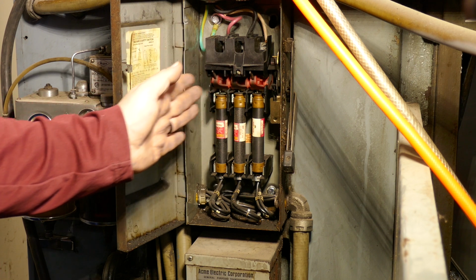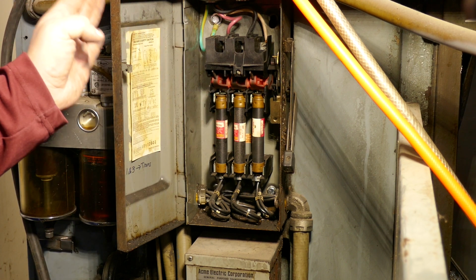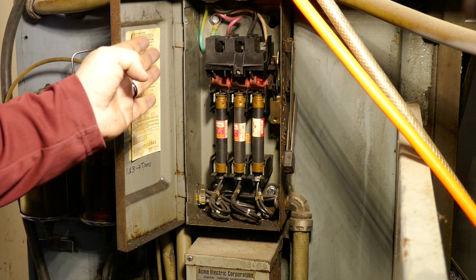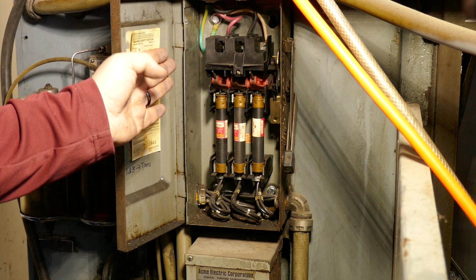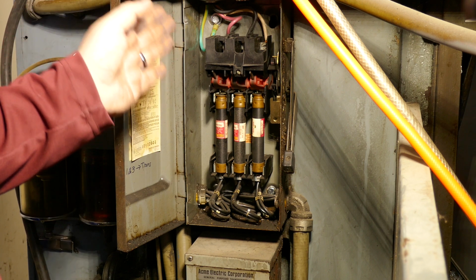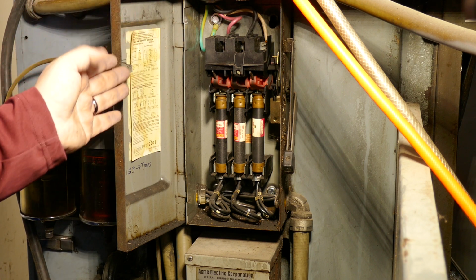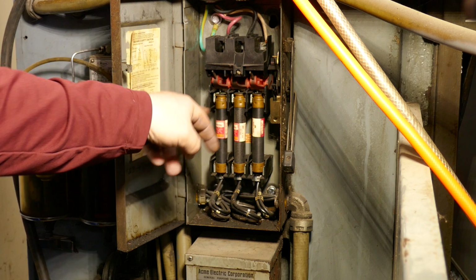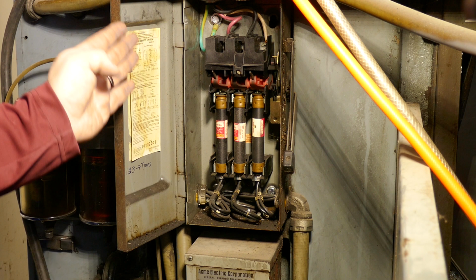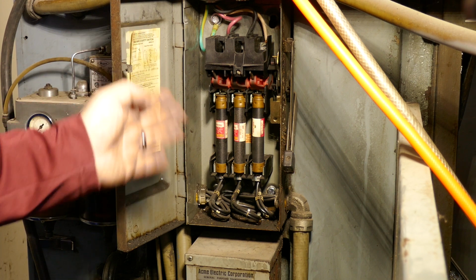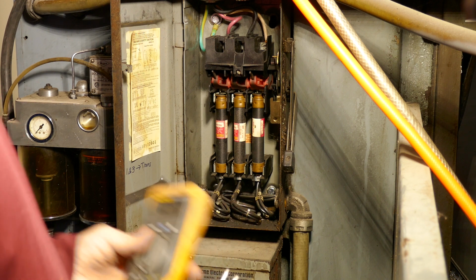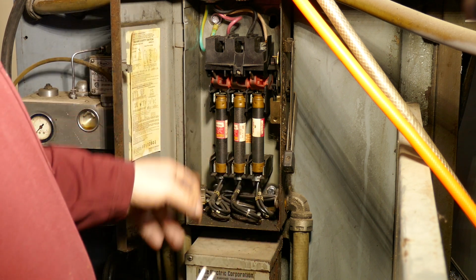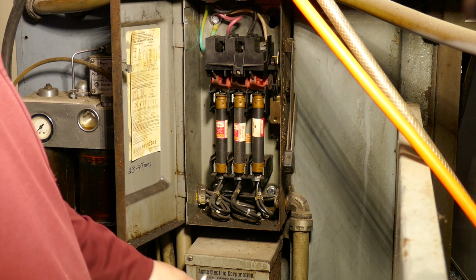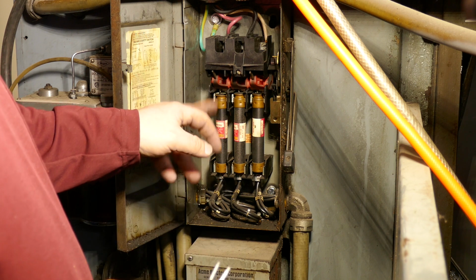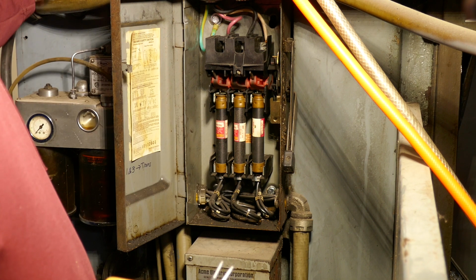That means if you measure between those two incoming legs from the power company, you're going to measure 120 volts to ground. What's different about a phase converter is that its output is not ground referenced. So if you measure the output of the phase converter to ground, you'll get 240 to 250 volts. So we're going to identify which of the three legs coming in are utility power and which one is the phase converter. Like I said, I want this transformer running off utility power, and I only want the generated leg, the wild leg, going to the spindle drive.